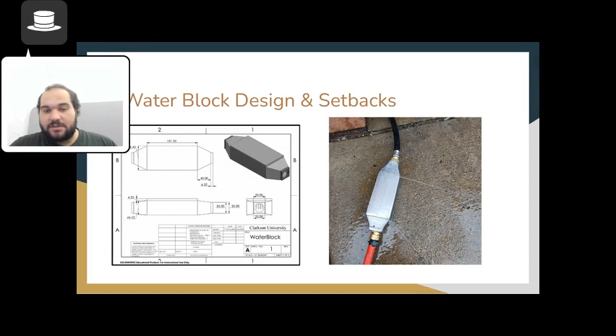The water block was fabricated using A36 steel pulled from the machine shop. All components were hand fitted and then welded at a lower voltage. This resulted in the water block leaking during pressure testing, as there was a lack of proper weld penetration in some areas.